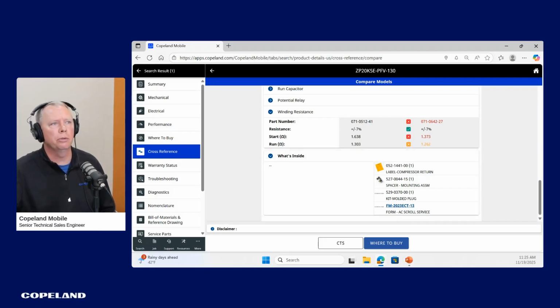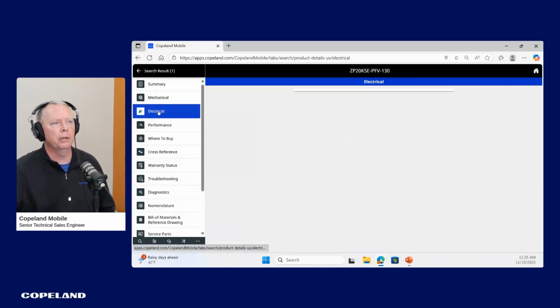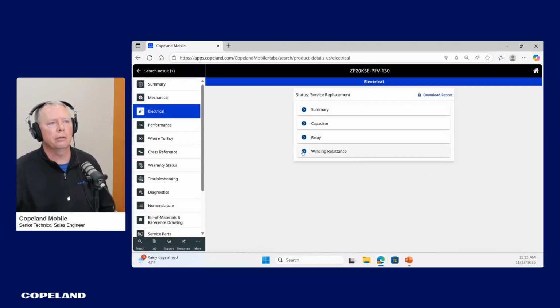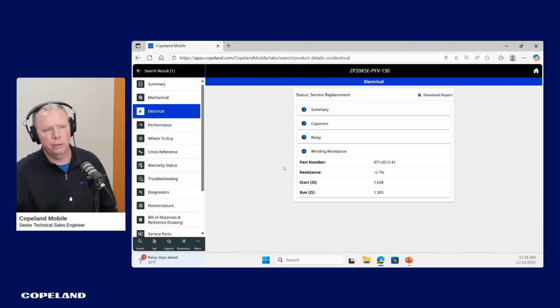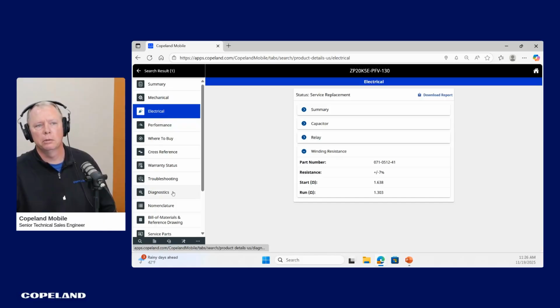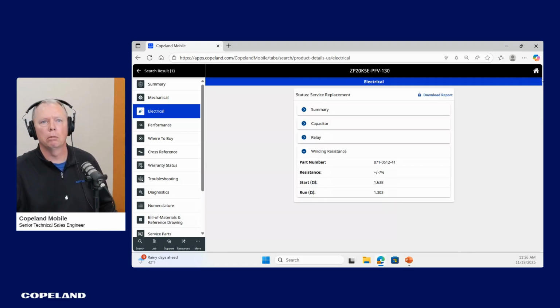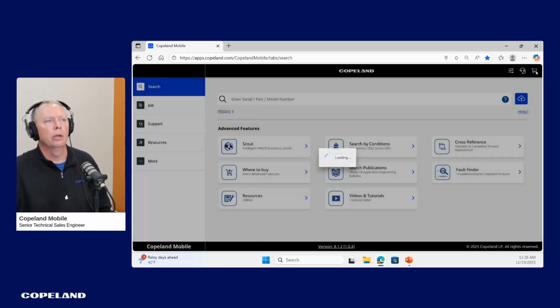One thing I wanted to hit on is when you're in the troubleshooting tab, like where John and I started, we were prompted to check winding resistance on that compressor. So under the original ZP20K5E, under electrical on the left side of the screen, it does provide what the winding resistance should be. So when you're prompted in troubleshooting, keep in mind the information they may be asking for on winding resistance is going to be available to you, under that model on the left side of the screen.